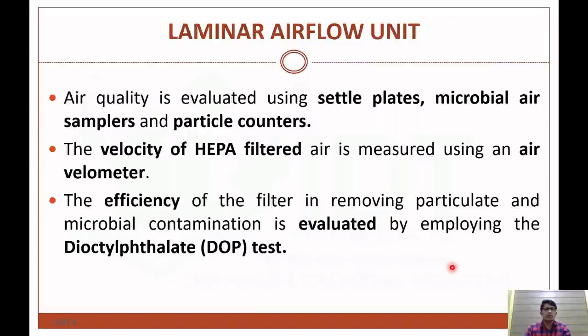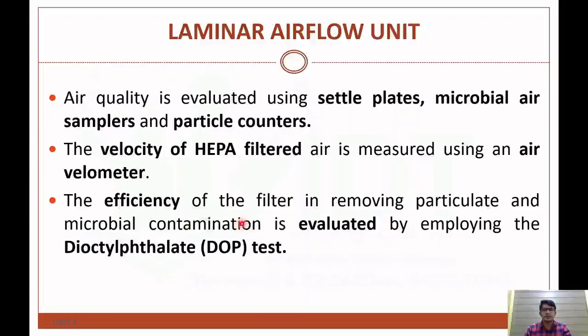Air quality can be evaluated by using the settle plate method, microbial air sampling method, or particle counter method. The velocity of the HEPA filter is measured using an air velometer, and the efficiency of the filter in removing particulate and microbial contamination is evaluated by employing the di-octyl phthalate test.